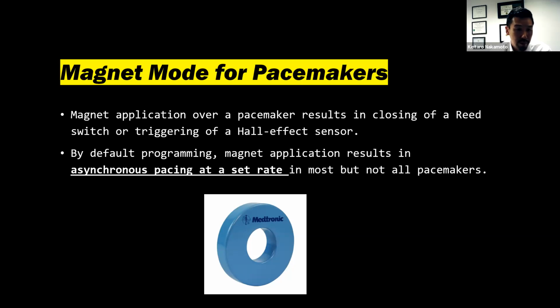By default programming, magnet application results in asynchronous pacing at a set rate in most, but not all, pacemakers. Asynchronous pacing is a mode in which the pulse generator delivers a pacing stimulus at a fixed rate, regardless and without any sensing capabilities. So regardless of EMI affecting the CIED, the pacer doesn't sense it when in asynchronous mode and continues to deliver a set rate of pacing.